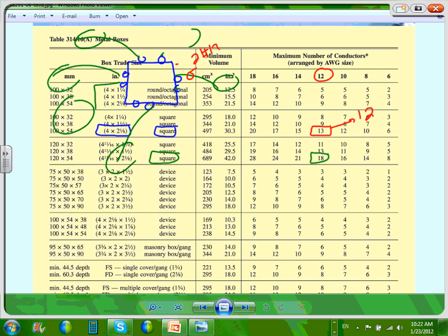And I'm talking about the J boxes right above the ceiling, guys, that you bring the EMT conduit to, and you feed all these lights from it. See how this becomes very handy without doing any calculation, because J boxes have nothing in them. They're EMT, so all what counts is the conductors. All what counts is a conductor.